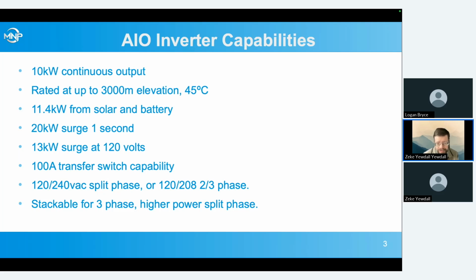100 amp transfer switch capability. We talked a bit last week about how doing whole house backup of 200 amp panels is not a great idea for a number of reasons. And that's one reason why we didn't opt to put a 200 amp transfer switch built into the inverter. If you want 200 amp transfer switch capability, you can do 2 of these inverters stacked, and then you've got 100 amps through each one. Or you can do some of the other things we talked about last week. But natively, we support a 100 amp transfer switch.